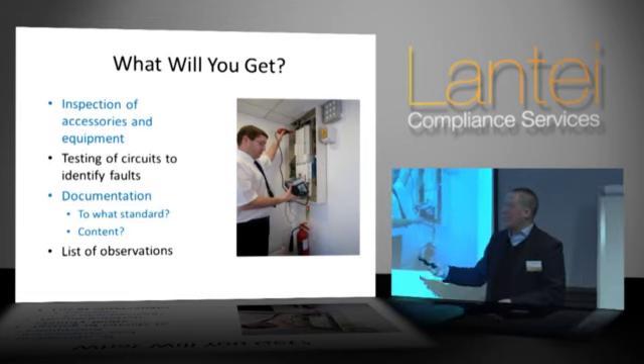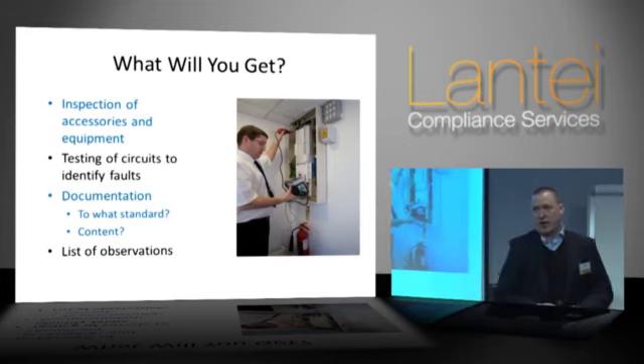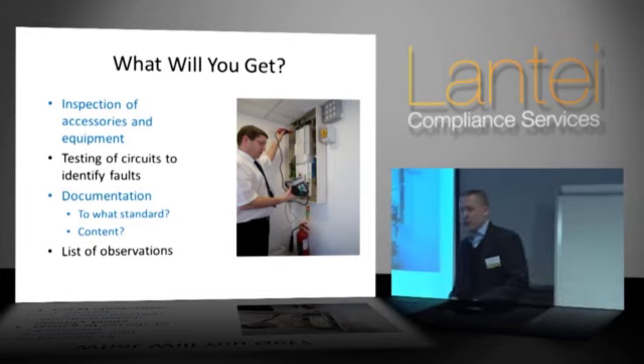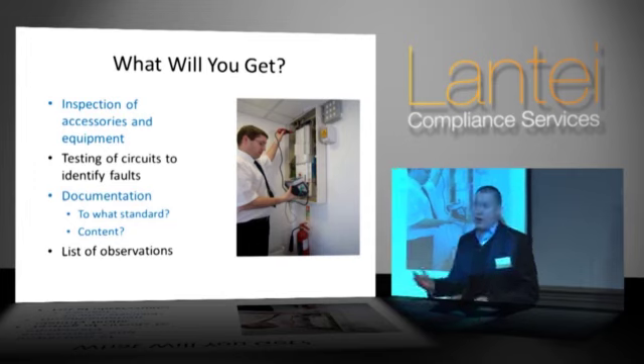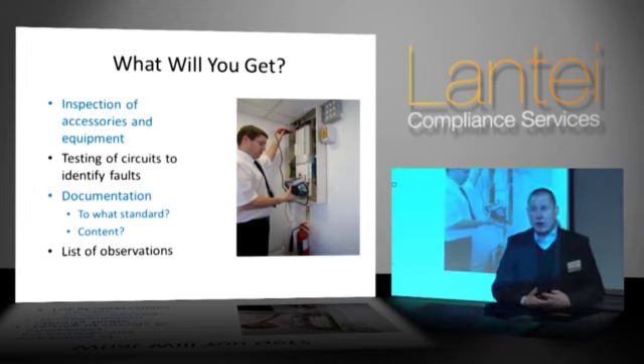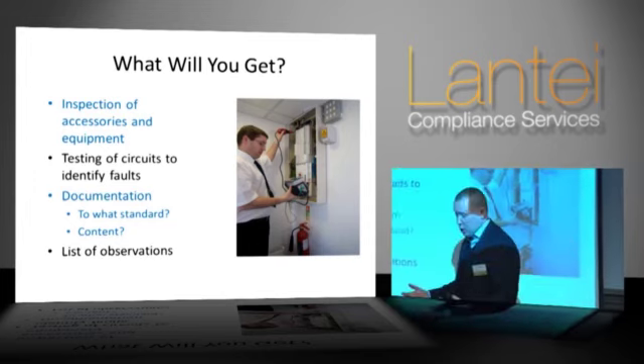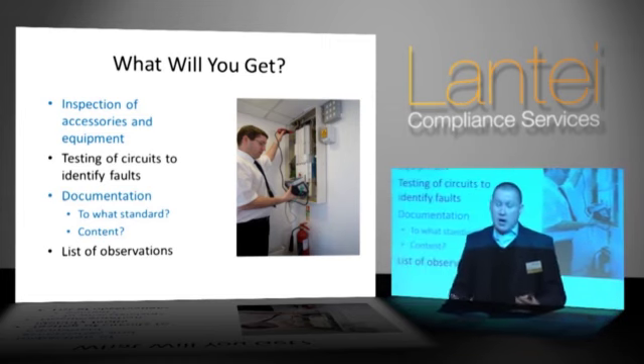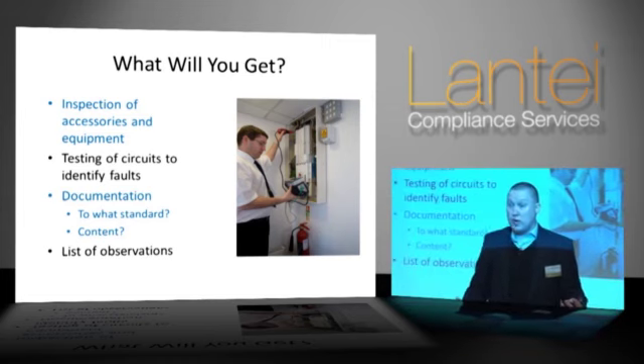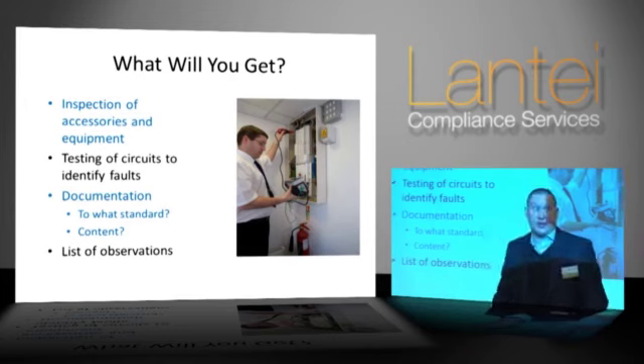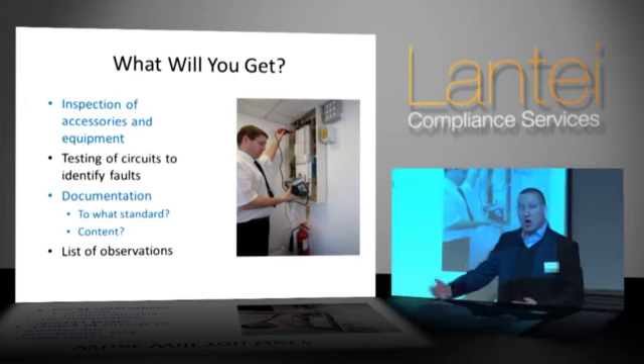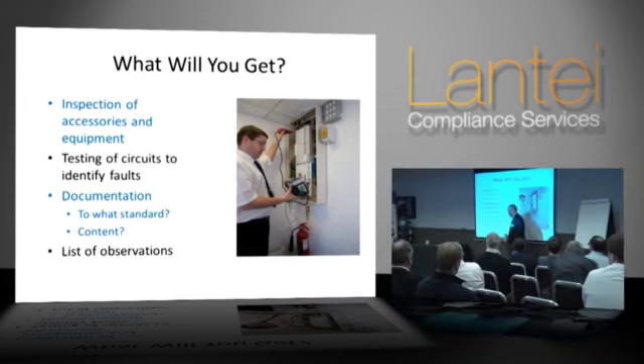What we're also looking for is testing of circuits. The reason we do testing of circuits is because we want to identify faults. So, very quickly, a couple of examples. We carry out insulation resistance testing because we want to see what the condition is of the insulation around conductors. We want to see if there's deterioration of the electrical installation. We carry out earth fault loop impedance testing because we want to make sure that the protective device for that circuit is going to activate in the case of a fault.